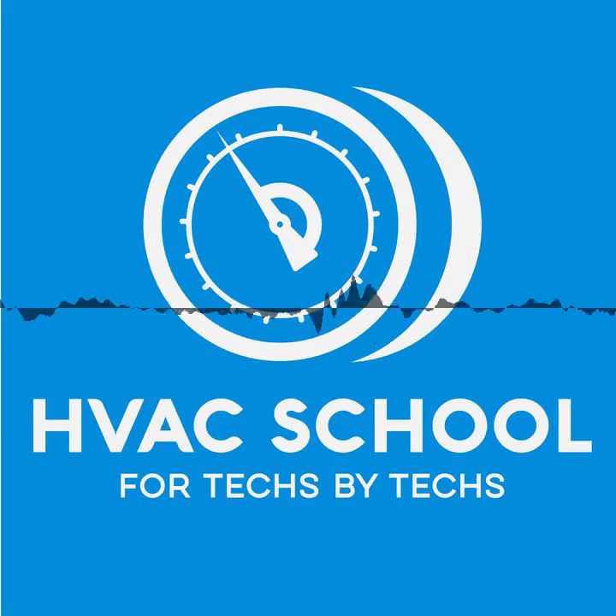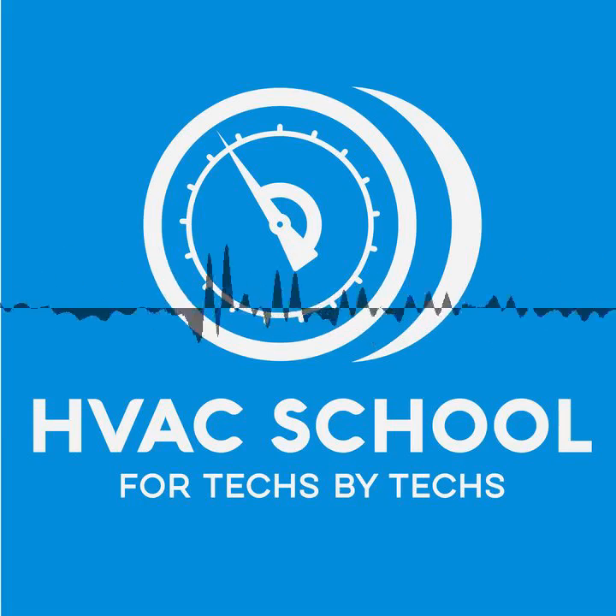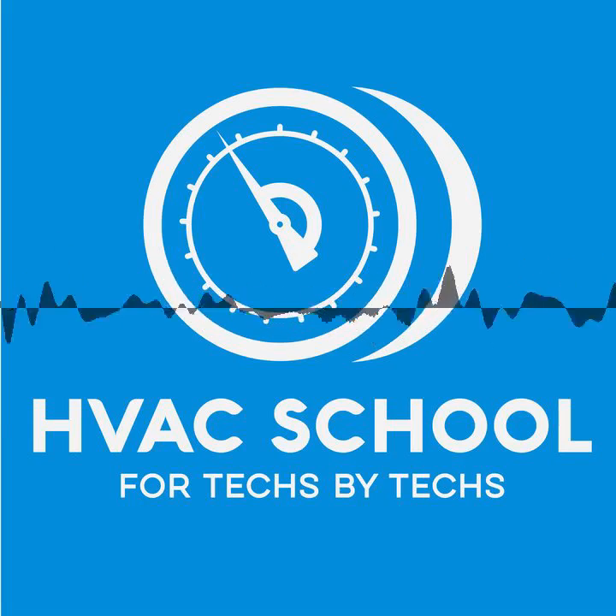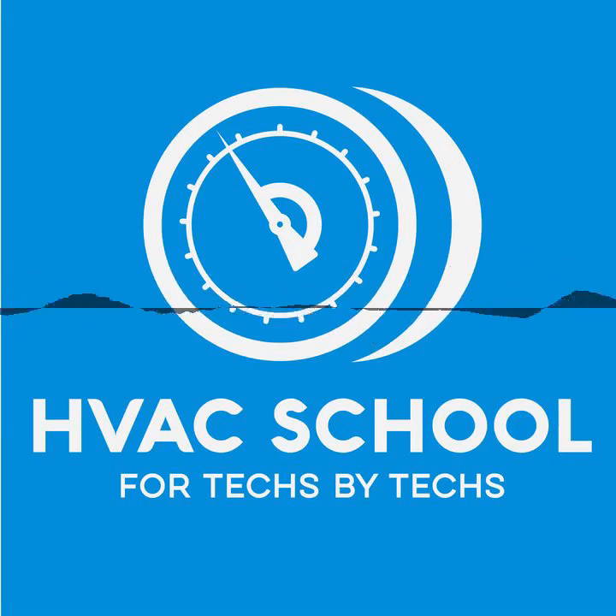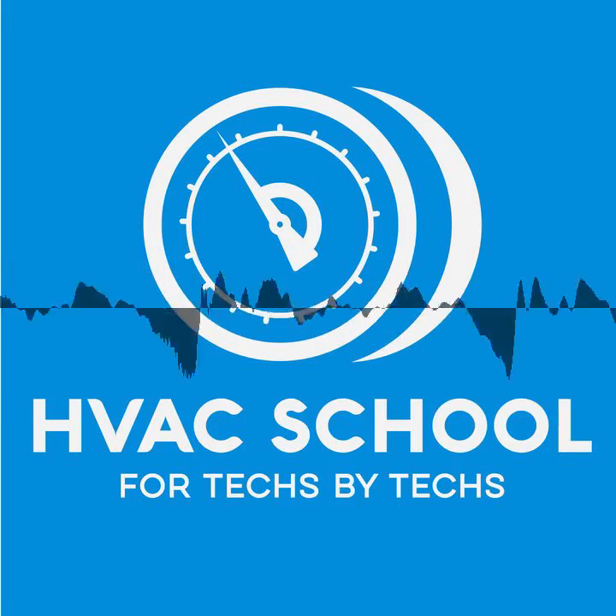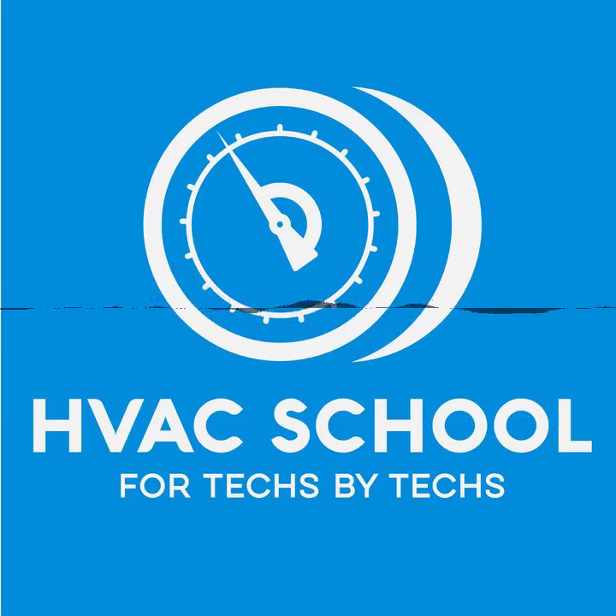So they're just setting a charge based on the charging information that the manufacturer provides, and they're wanting to make sure that the correct CFM is being produced. So the correct fan tap in the old way of thinking of it. And so that's sort of the simplistic way of looking at it, because the installer's not necessarily, or generally not, going to do delivered capacity tests. They just get everything within range, and there's the assumption that the equipment's working properly. And again, that's just standard practice. Maybe some people will say, well, our installers do that type of testing every time.